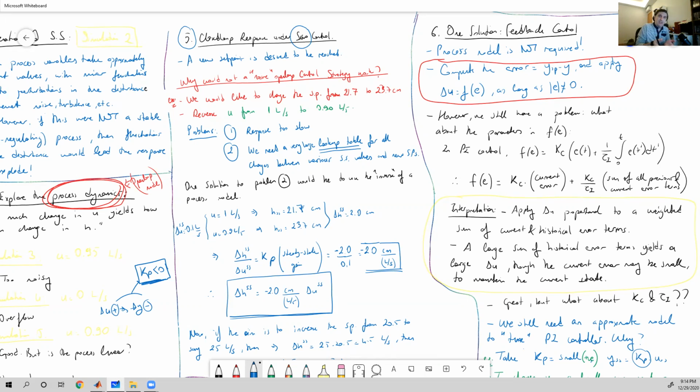This is less often, because the requirement to change the set point depends on a couple of things, maybe some changes in the economic conditions, or maybe demand, the increase or decrease in the production, or things like that. On the other hand, almost every second or maybe every minute, or at least in a much more frequent manner, there are going to be perturbations in the disturbances. So therefore, the primary aim of the controller should be to hold the system at the preset set point, in spite of those disturbances. And therefore, regulatory control is the more common control, whereas servo control is the less frequently applied control, let's say.